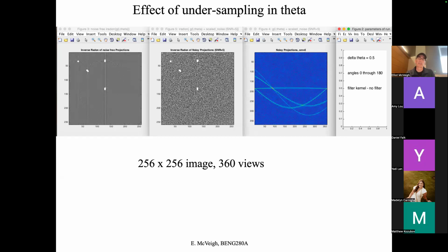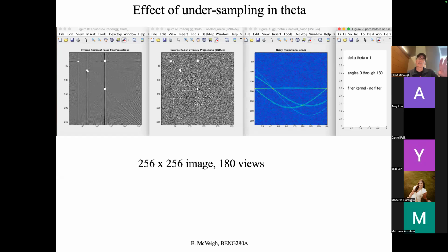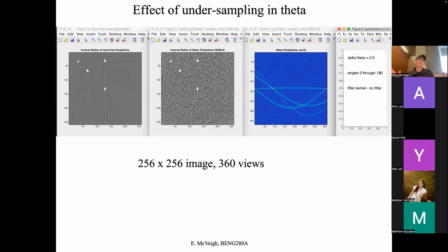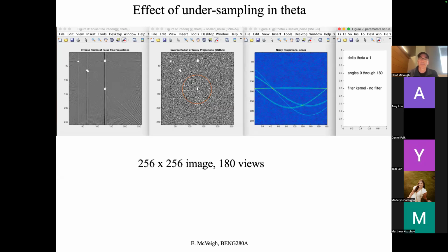But principally what's happening is that the 1 over m term in the signal to noise, or the variance, is kicking in. From 180, I get a picture with a certain background variance. It looks kind of hashy. If I do 360, I don't really change the picture, but the noise goes down. And then 720, same deal. The noise just keeps getting better.